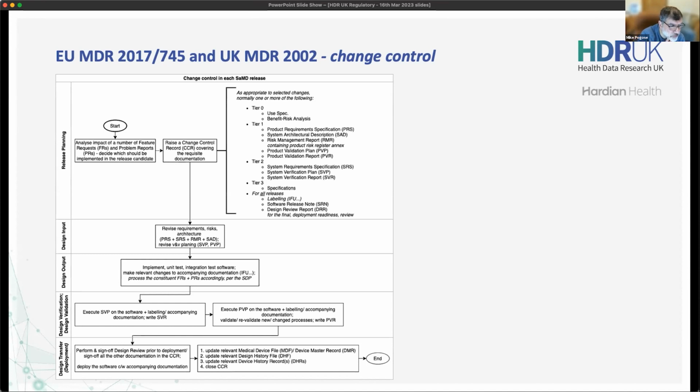So what's the conversation you've been reacting to in the... Yes, so Sharon, strictly speaking, changing a predictive model will be a significant change because you're changing the basic design of your product. But this is where we talked about algorithm pre-specification and algorithm control protocols earlier. Someone asked a question about it. I think what we try and do is create the argument for your quality management system with the notified body that you are so good at specifying your product, you're so good at controlling the process, doing things like this, that's on the screen, that they will trust you until they come back for the next annual surveillance visit.